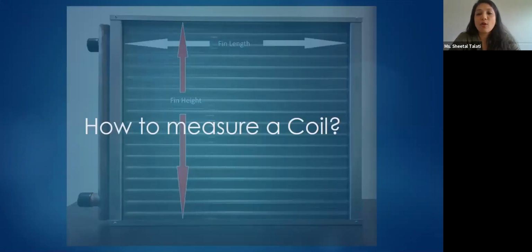Now, how do you measure a coil? First, you measure the coil from fin to fin. You take the fin to fin height and the fin to fin length. If you ask any local manufacturer, they have the diagrams of set brands like Blue Star, Carrier, Voltas. If you ask, can you make a 7.5 tonner coil, or an 8.5 tonner Blue Star, or an 11 tonner, 16 tonner, 7 tonner? Those ductable unit or split unit coils are very easy, and they have a set diagram. So for that, we do not ask for a sample or any kind of diagram.